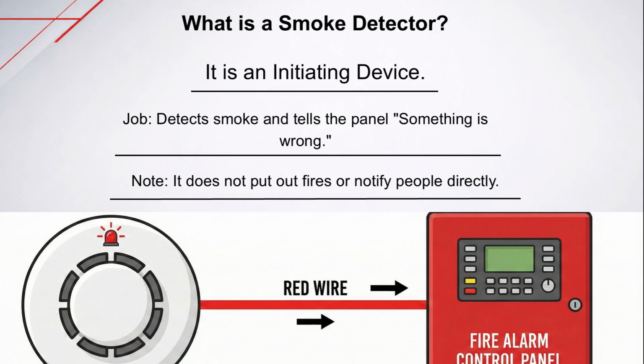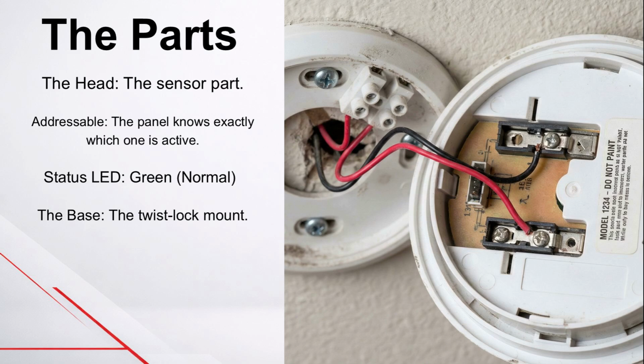take action. Physically, a commercial smoke detector is usually made up of two distinct parts, the detector head and the mounting base. The head contains all the electronics, the sensing chamber, and the brain of the device. The base is what connects to the field wiring and allows the head to be twisted on or off for maintenance. You will also see a status LED on the face of the device. Typically, a flashing green light means the device is normal and communicating with the panel. Most modern systems use addressable smoke detectors, which means the panel knows the exact location of every single device.